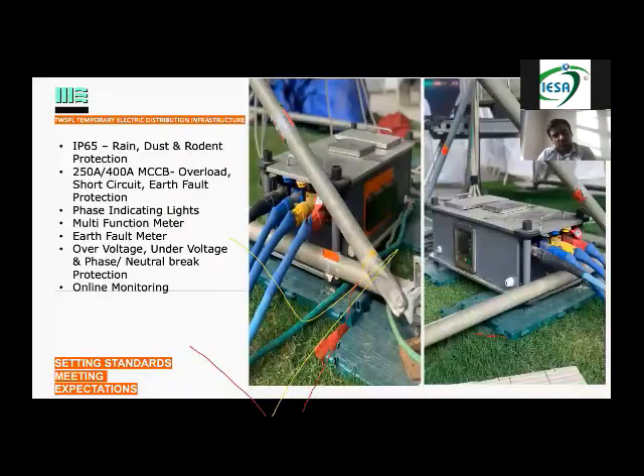So this is a junction box that we created maybe a year back. This is for the bulk power. When I say bulk power, it means that maybe your AC guy or your sound, light, LED guy has asked for bulk power. He says that for this dedicated genset or this dedicated load, just give me the power over here, don't distribute it. So these panels, which we call junction boxes, are all IP65. They are enclosed.